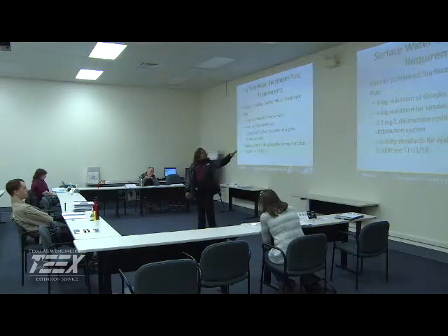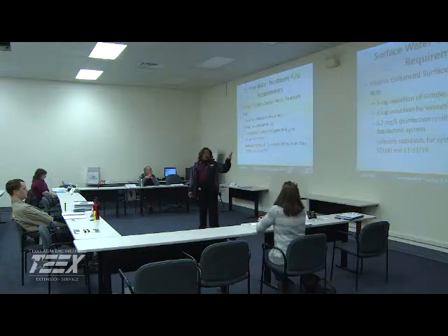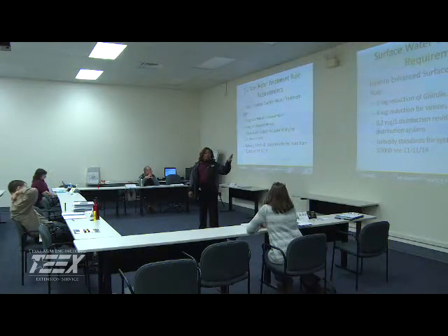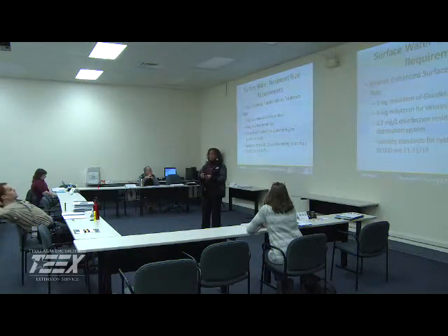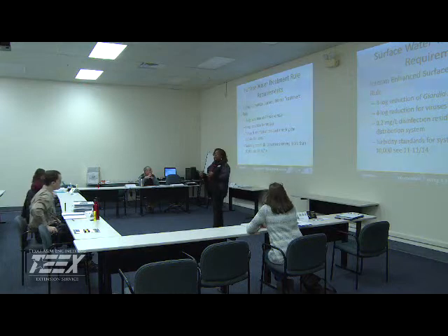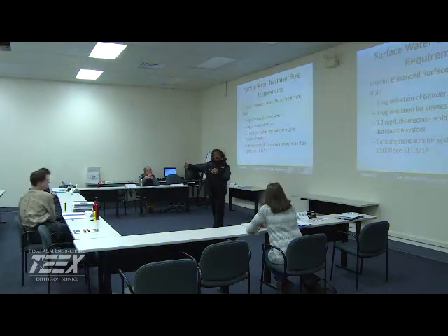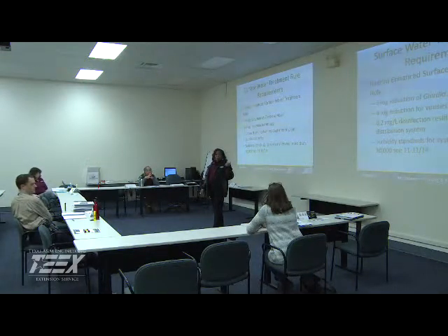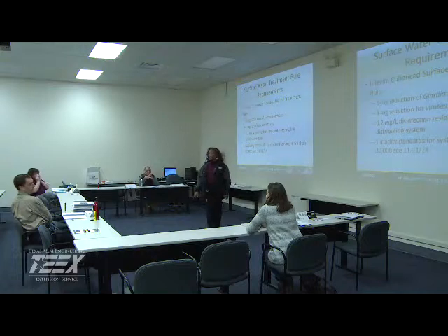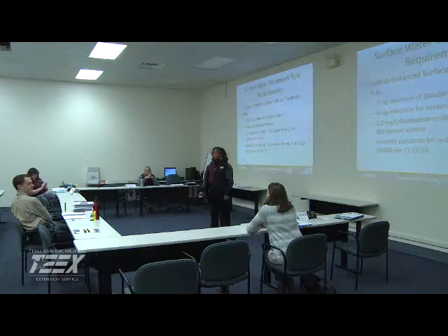Now, keep in mind, this right here is just the minimum, and although we say 0.2, that's not our target point by no means. Because if you look in our rules and regs, at the farthest reach of the distribution system, we should be achieving the 0.2. That's where our 0.3 comes in. We should probably be issuing violation letters if we get results saying they're less than 0.3.